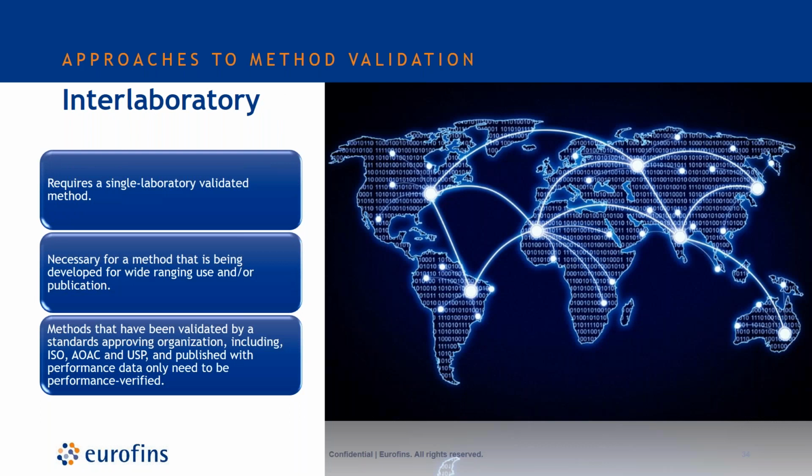A collaborative study or interlaboratory comparison is the most generally applicable for a standard method. Collaborative studies are multi-site studies that are directed by a pre-approved protocol and have defined procedures and acceptance criteria. Contributing laboratories submit a report and results are evaluated against the acceptance criteria. Results from a successful method trial are published and the new method is considered to be fit for purpose. After the collaborative study, the method may be implemented by a method transfer, which includes a comparative study between the reference and participating laboratory or laboratories, or by completing a compliant method performance verification, which we'll talk about more later.